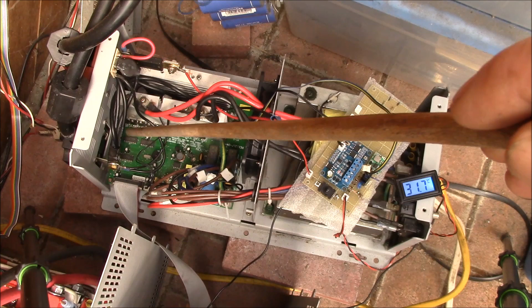You've got the relays, a filter, a bunch of MOVs and surge suppressor type circuitry, and also voltage monitoring to decide when the input voltage has gone low enough that it needs to switch over to inverter mode. The rest of the circuitry here is basically all of the inverter and charger logic - it does all the switching, controlling, generating waveforms, charging the battery, and deciding what to do. Let's look here.